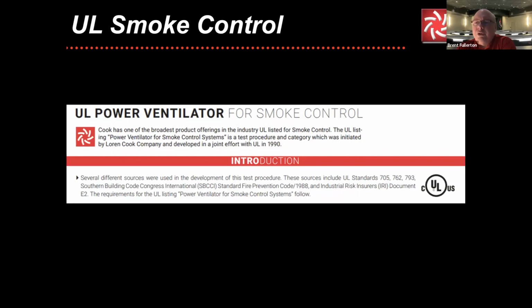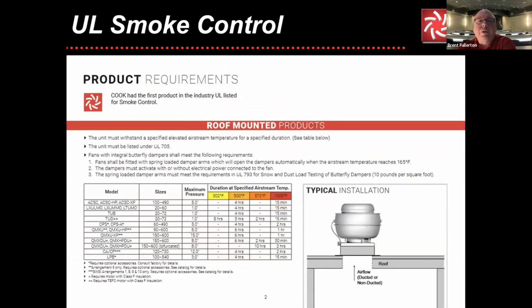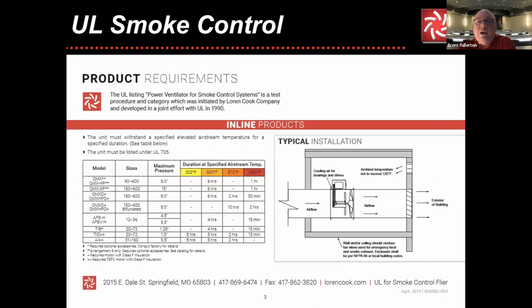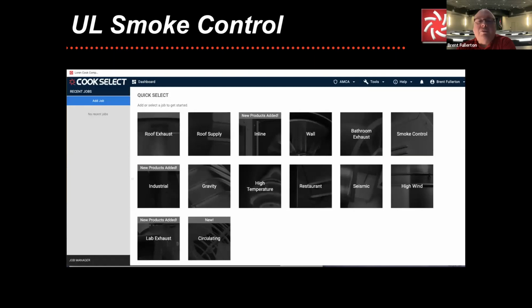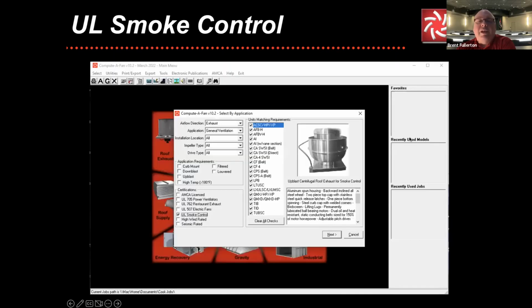Pre-1990, there were a lot of regional codes that came up, were here and there, and that caused a lot of grief and heartache, not only for the consultant, also the design build contractor, and even some code officials, and definitely for the manufacturers and the representatives. So this came about to be a level document that pulled a lot of different sources. So roof mounted, inline, all that. Once again, we did a little bit more of a deep dive on that last month. Once again, the software will go back and allow you to, over on this side, smoke control, make selections. And this is our installed version of the software, and you can see these selections from there.